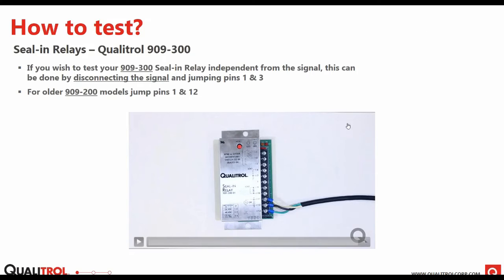And last but not least, we're going to look at the seal-in relay that we offer. The seal-in relay is designed to take in a momentary switch contact and seal that signal in for an alarming or trip function. These are typically paired with our rapid pressure rise relays because those have a momentary switch action. When the sudden pressure rises, it actuates that switch, and then the RPRR will settle back down, or the pressure will be relieved through some other means. Then you want to keep that alarm or trip signal because that was a serious event that occurred. That's what this seal-in relay comes in handy for.